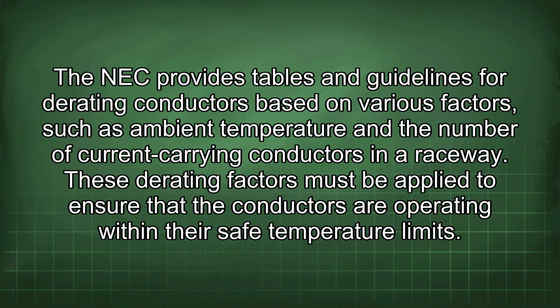The NEC provides tables and guidelines for derating conductors based on various factors, such as ambient temperature and the number of current carrying conductors in a raceway. These derating factors must be applied to ensure that the conductors are operating within their safe temperature limits.